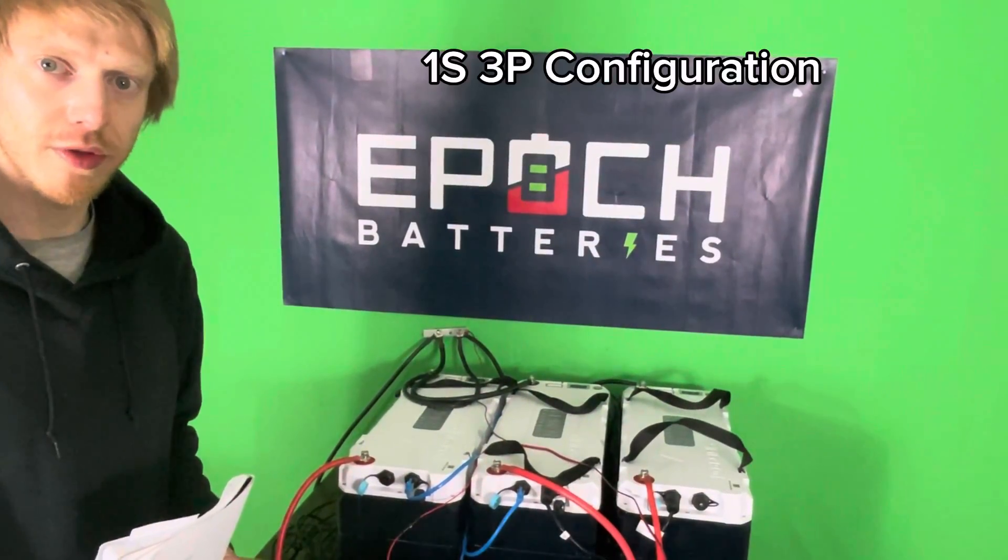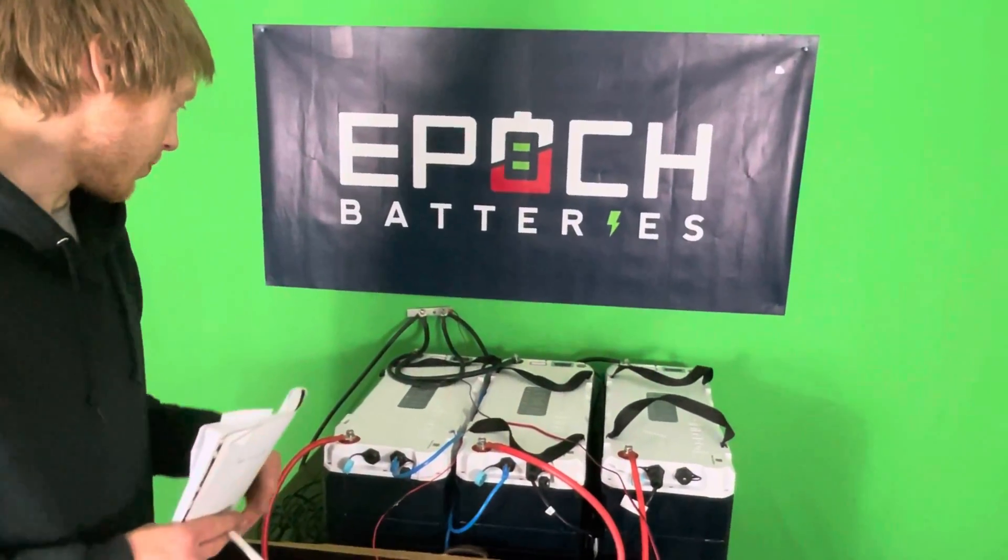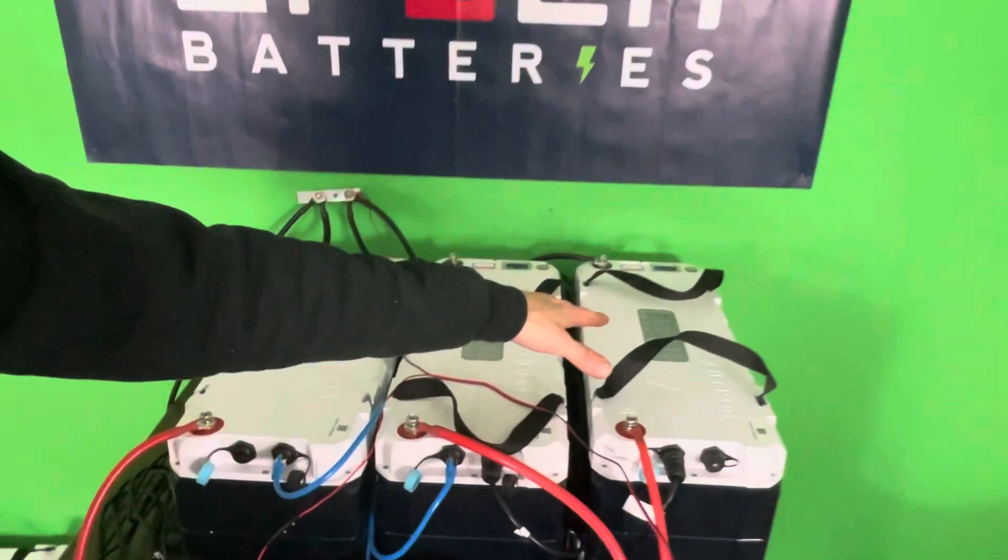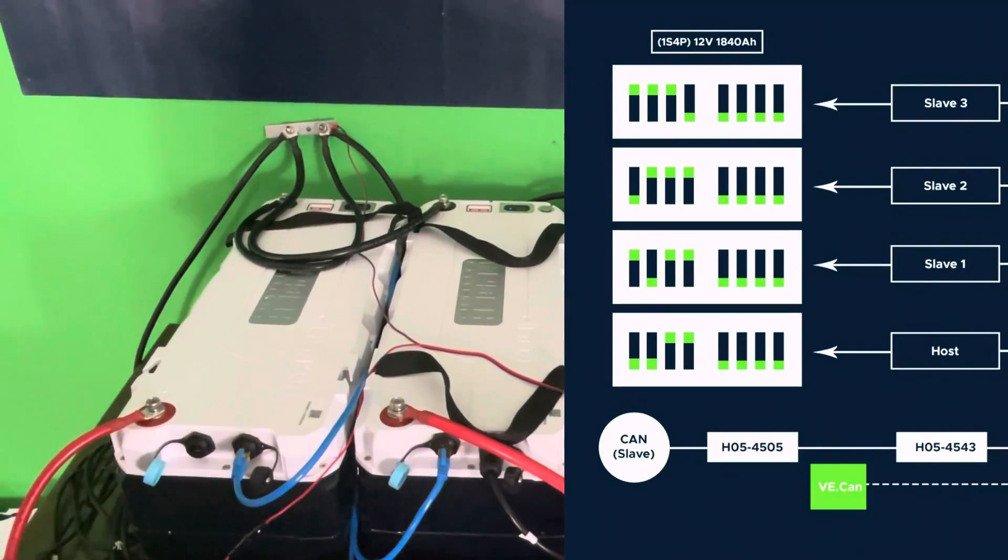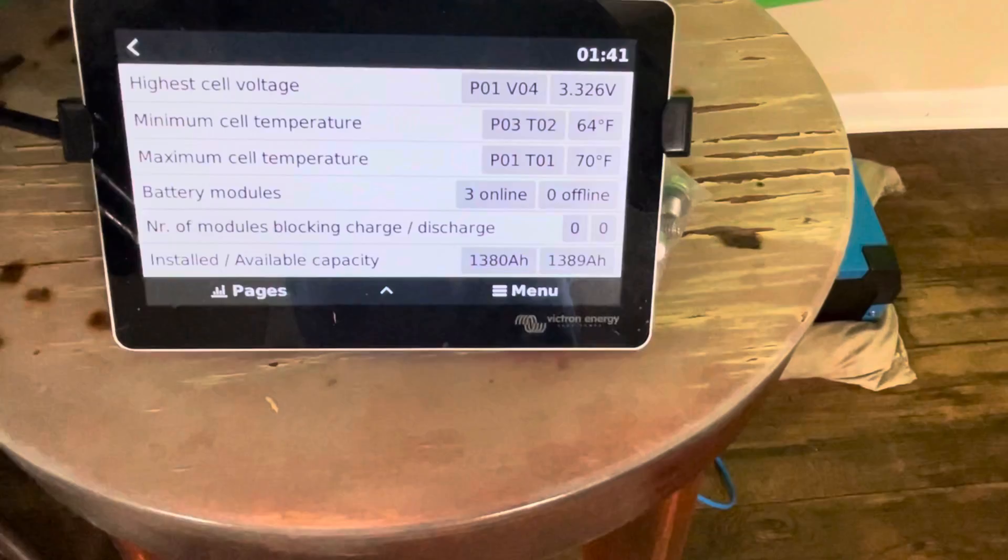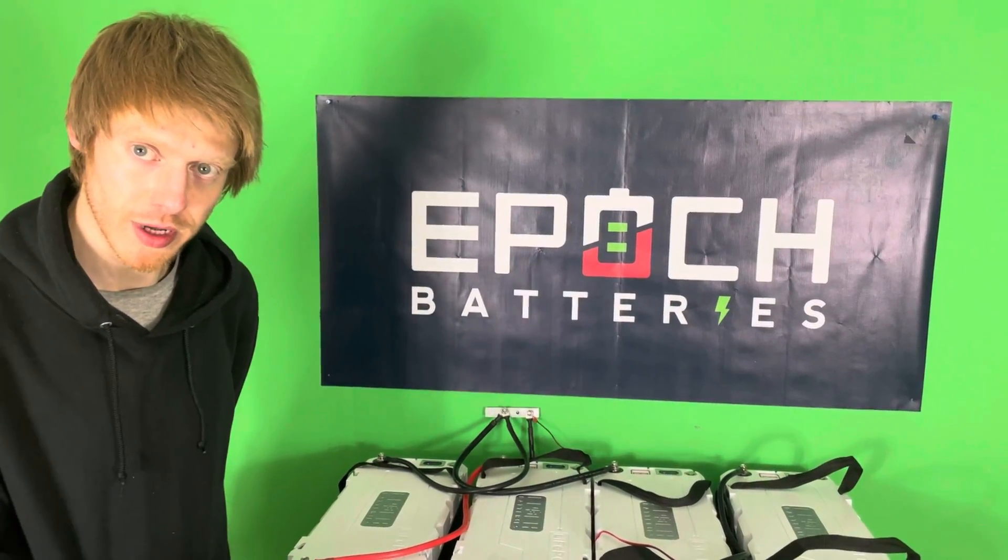Alright, so now we're going to discuss the 1S3P configuration, which is going to be each of these in parallel. And you can refer to the dip switch settings on the screen to adjust those accordingly, and to verify we can look up again over the Cerbo and see we have 1380 amp-hours. So that's all for this configuration and now on to the next.